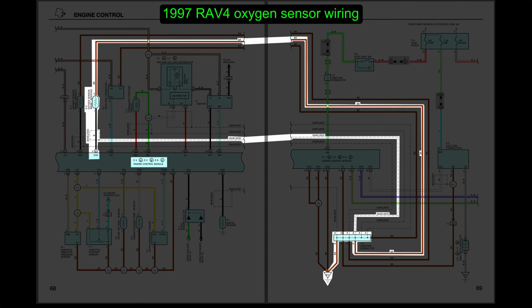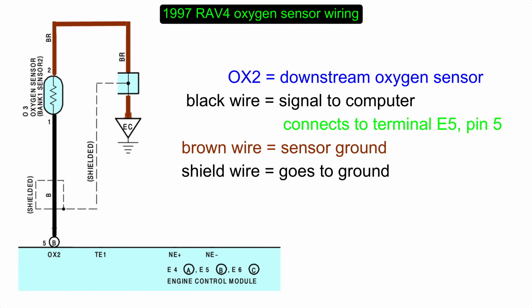This diagram is hard to read like this, so let me simplify it. Okay, the black wire is the signal, and it connects to pin 5 on terminal E5 on the ECM. The sensor wire is shielded. That means it has a layer of aluminum foil around the wire that conducts electromagnetic interference, then grounds it so it doesn't get into the signal wire. The brown wire also connects to ground.